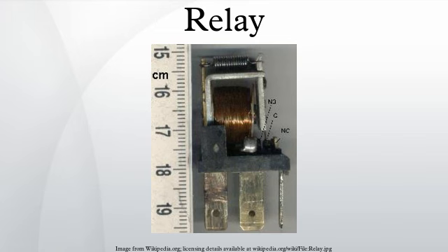Isolation between coil and contacts, aerospace or radiation-resistant testing, special quality assurance. Expected mechanical loads due to acceleration: some relays used in aerospace applications are designed to function in shock loads of 50 G or more. Size: smaller relays often resist mechanical vibration and shock better than larger relays, because of the lower inertia of the moving parts and the higher natural frequencies of smaller parts. Larger relays often handle higher voltage and current than smaller relays. Accessories such as timers, auxiliary contacts, pilot lamps, and test buttons, regulatory approvals, and stray magnetic linkage between coils of adjacent relays on a printed circuit board.